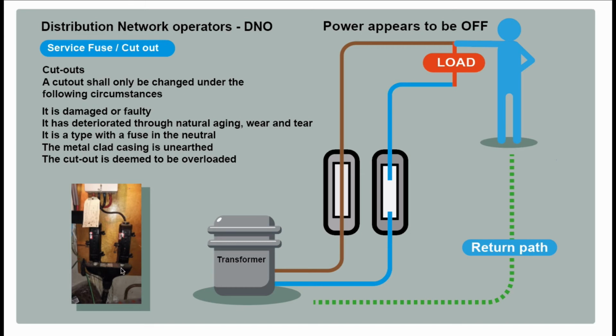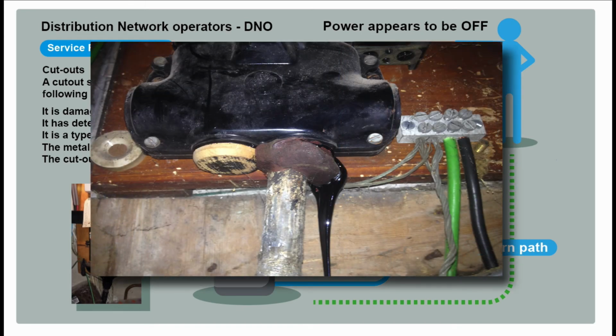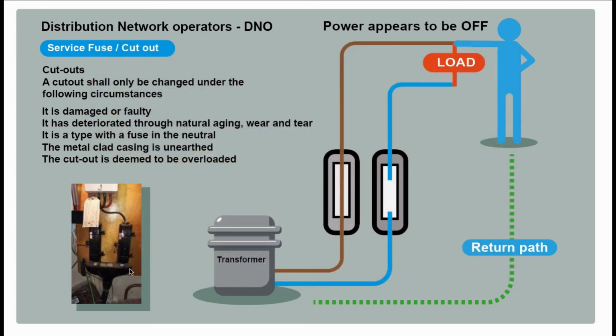Quite often you see black pitch dripping out of the service head, and that's a good indication that things are too hot inside the fuse, a loose connection or whatever, and the actual pitch inside is starting to melt and drip out. So if you see that, call the DNO, and they'll come around and investigate. They'll be around quite quickly.